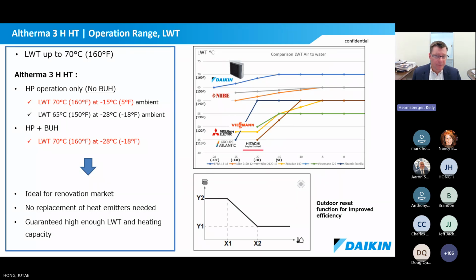And then I think lastly, I'll just leave you with a little bit of an emphasis on performance before we go into the discussion on field trials. What I love about the system, it's called Altherma 3 HHT. That's high temp. The hydro is the first H, and then HT is high temp. But what we'd like to talk about here is that you can get the leaving water temperature at 160 degrees at -15 ambient with just the heat pump solution only. And then the heat pump plus the backup heater would get you down to the -18 Fahrenheit environment with a leaving water temperature of 160 degrees. That's strong performance. It's not only good for renovation to remove boilers, but it's just a really smart design if you want the comfort of the premium in-floor radiant heating, high performance COP system.